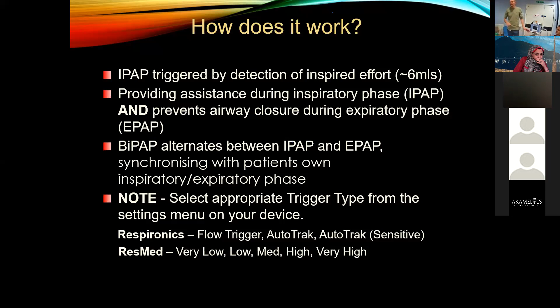Okay, so Auto-Trak will be triggered by 6 mils of inspired air. Okay, Auto-Trak Sensitive will be triggered by 3 mils of inspired air. Okay, good for pediatrics, good for patients with a very weak respiratory drive. With your ResMed machines, your trigger type settings are different. They're just called very low, low, medium, high, or very high. Okay, again, I've actually managed to find some user guides for the ResMed Air Curve device and the BiPAP AVAPS Respironics device. So if needed, I can get them sent to Saeed and he can circulate them amongst you guys.